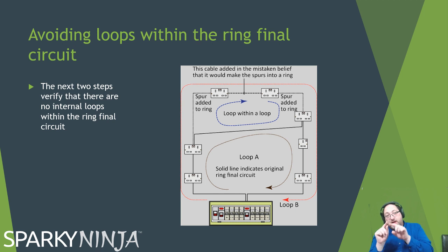the first reading we had, which was line plus neutral, the reason we've divided by 4 is when we go around going from line to neutral at each socket, the pathway of that measurement has halved, because it's no longer this loop of line plus this loop of neutral, it's just this half loop of line and neutral. So the length has halved. We're also going from one conductor in each terminal, or each connection of line to line or neutral to neutral, to 2, because there are 2 neutrals and there are 2 lines in each terminal. So the length has halved, halving the resistance, and the cable size of the measurement has doubled because there are now 2 cables under the test probe. So if the cable size doubles, that halves the resistance. If the cable length halves, that halves the resistance.